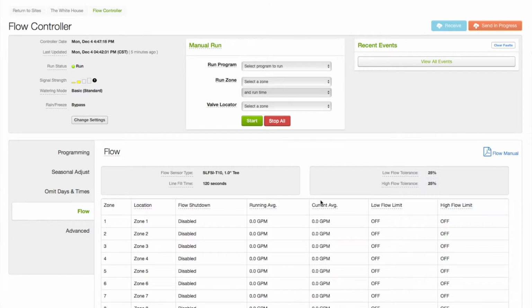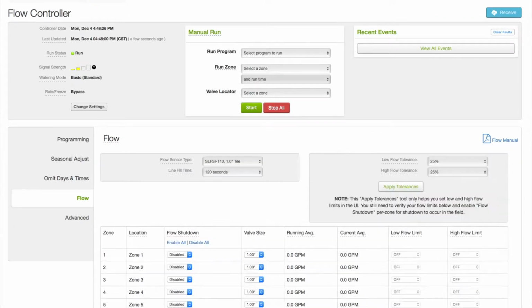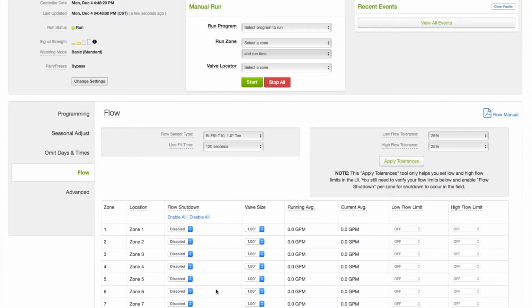So once we've let the controller run for about 5 run cycles, this current average will start to populate. And we'll get an idea of what these flow rates are and what our thresholds can be. So when I want to edit these flow settings, bearing in mind that flow sensing is already on, I can enable the alert, and that will open these windows for the low limit and the high flow limit.